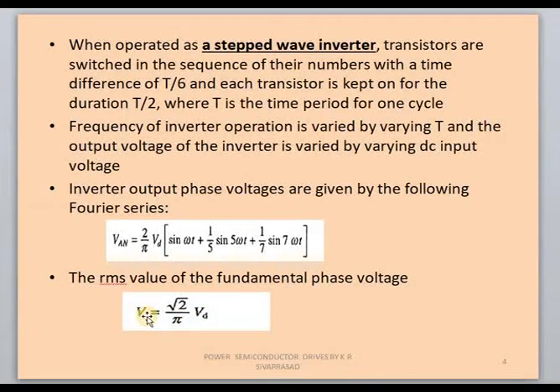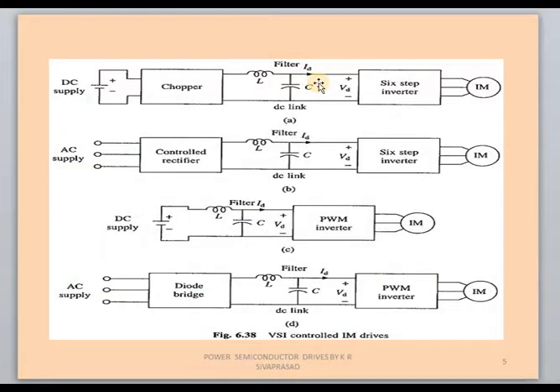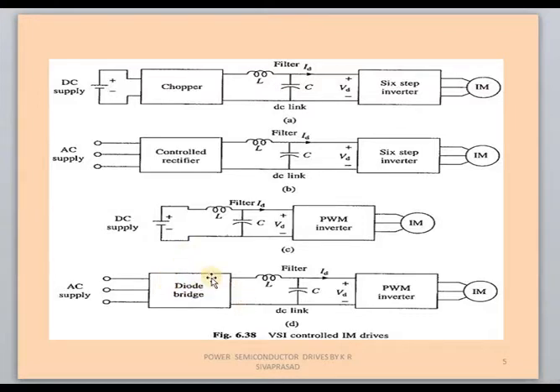These are the different schemes of controlling induction motor speed, because we need variable voltage and variable frequency. All four schemes produce variable voltage and variable frequency. In the first two diagrams we use a square wave inverter; in the next two diagrams we use a PWM inverter. For the PWM inverter, a diode bridge is sufficient — no controlled rectifier is needed, since the PWM inverter itself produces variable voltage and variable frequency. The diode bridge converts three-phase AC to DC, and harmonics are filtered using a DC link.